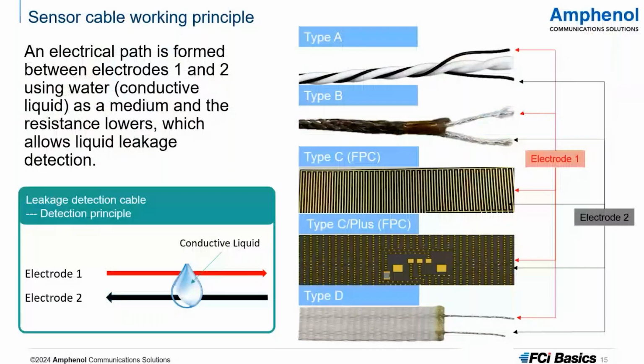Currently, we have 5 types of sensor solutions. As you can see, even though they have different shapes and structures, the working principle is almost the same. There are 2 electrodes, formed between electrodes 1 and electrodes 2. You see these electrodes 1, 1, and 1, and electrodes 2, 2, and 2. As soon as conductive liquid drops onto the cable, the 2 electrodes will be immediately shorted. Then the resistance between the 2 electrodes will be much lower, and the leakage can be detected by the system. This is the working principle of this leak detection sensor cable.